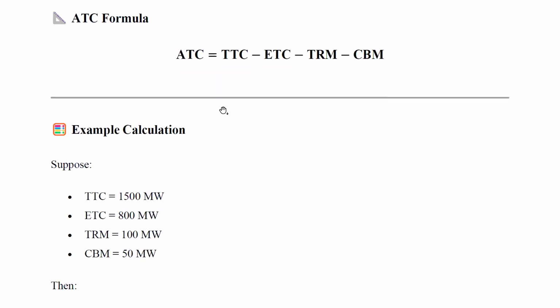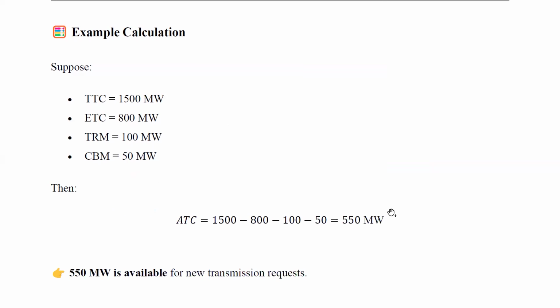For example, TTC is 1500 megawatt, ETC is 800 megawatt, TRM is 100 megawatt, CBM is 50 megawatt. How to calculate ATC? ATC equals TTC minus ETC minus TRM minus CBM. So 1500 minus 800 is 700 megawatt, minus 100 is 600, minus 50, that is 550 megawatt. So total is 550 megawatt.